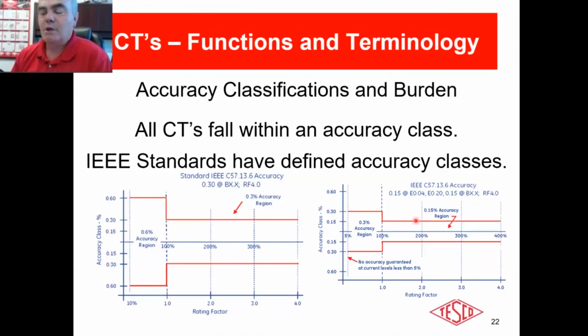Less than 1. If I have 2, 3, or 4, it means that I can go to double, triple, quadruple. If I have less than 1, that means I can't even go up to what the faceplate says I can go up to. Well, what the heck is the point of that? Why don't I just be honest with you and tell you, no, I can't go up that high? In some of your very largest transformers, you can get a rating factor of less than 1. What does it mean? I've seen 6,000 to 5 and 8,000 to 5 current transformers that had thermal rating factors of 0.8 and 0.9 and 0.7.